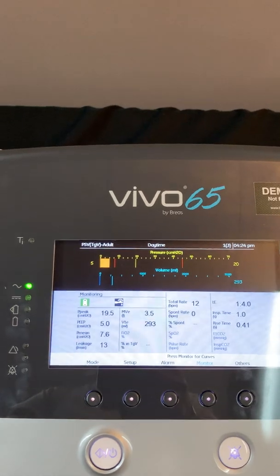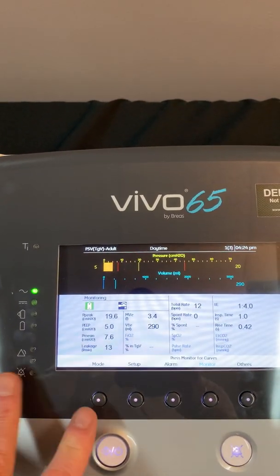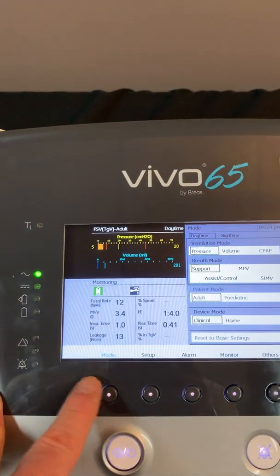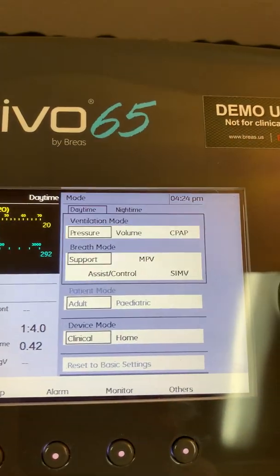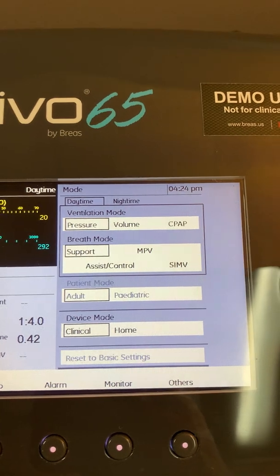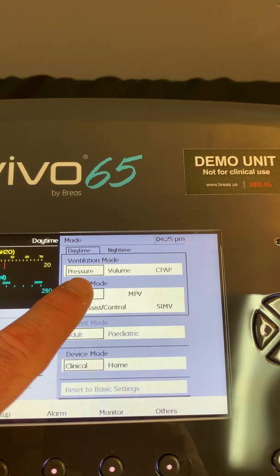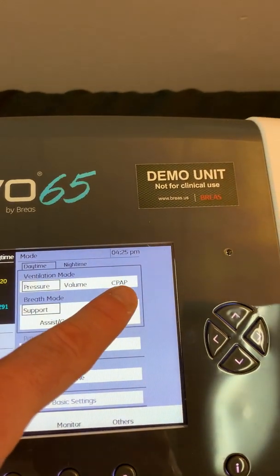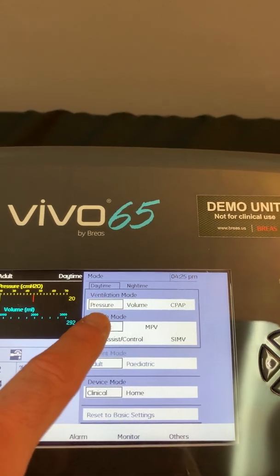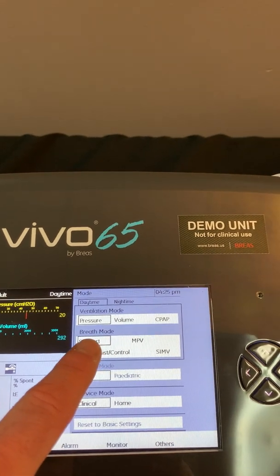Over the next few minutes I'm going to go over the mode menu. To get into the mode menu itself we're going to press the mode menu button, and that opens up our options as far as what our mode choices are. At the top you'll see we have a ventilation mode, we have pressure options, we have a volume option as well as a CPAP option. I currently have a box around pressure so I'm currently in a pressure mode, and then down here I have a choice for my breath mode.